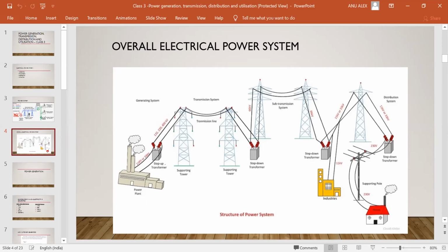Once it comes to this transformer, you can see it is a step-up transformer. What will it do? It will increase the voltage at the output side from 11 kV to a very high voltage, like 132 kV or 220 kV. Usually this stepped up voltage will be in multiples of 11, because the voltage generated is 11 kV, and it is easier to create a turns ratio that way.